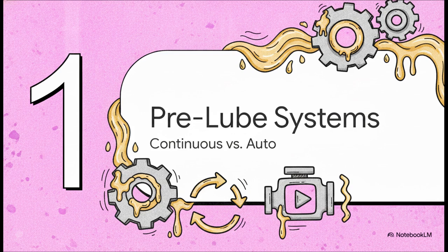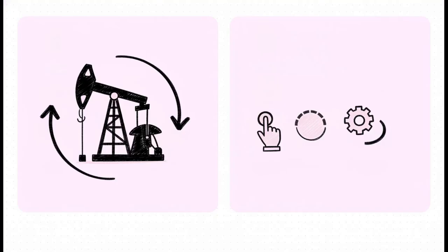You see, before a massive engine like the C175 even thinks about cranking over, it absolutely needs a protective oil film. Without it, you get catastrophic metal-to-metal contact on the internal bearings, and the C175 actually achieves this protection through two totally distinct automated systems. First up, we have the continuous pre-lube system. This is used pretty much exclusively for standby or critical applications. And I mean continuous. It literally never stops running. It pumps oil 24/7. Now, why do this? Well, you're basically accepting the trade-off of constant pump wear to guarantee instant readiness.